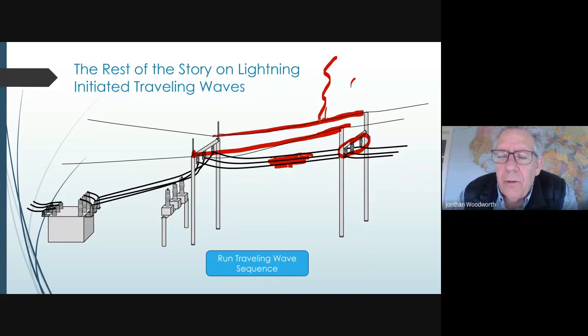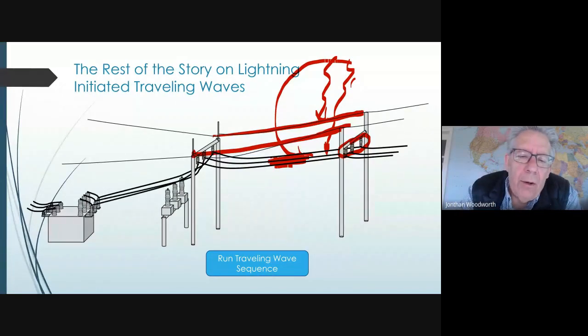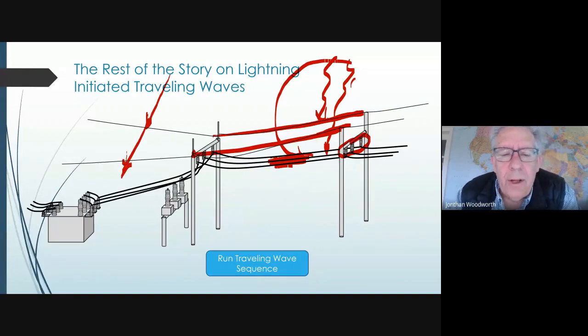It's a lightning interceptor. If the shield is working properly and designed properly, the surge will never get to the phase conductors. We design the systems so that we have very few times, maybe once in 20 years or once in 100 years, that the surge can get around and get to the phase conductor. It never gets through the shield into the substation. We don't even take that into account. The shields are very effective.